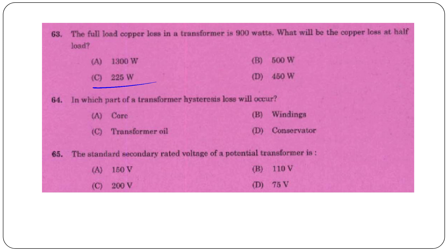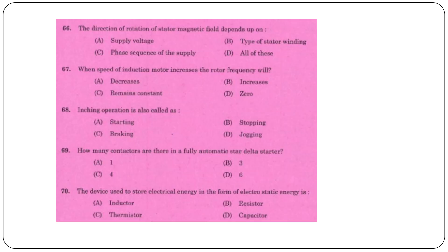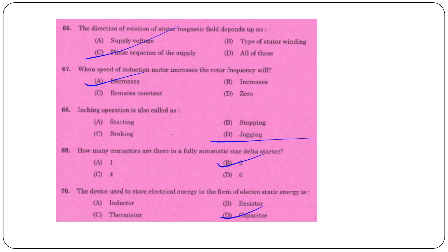Maximum efficiency condition in a transformer: copper loss equals iron loss. Full load copper loss is 900W; half load copper loss is 225W (= 900/4). Hysteresis loss in a transformer occurs in the core. Standard secondary rated voltage of a potential transformer is 110V. Direction of rotation of a stator magnetic field depends upon the phase sequence of the supply. When speed of an induction motor increases, rotor frequency decreases. Repeated short jogging is called inching. A fully automatic star-delta starter has 3 contactors. The device used to store electrical energy in electrostatic form is a capacitor.